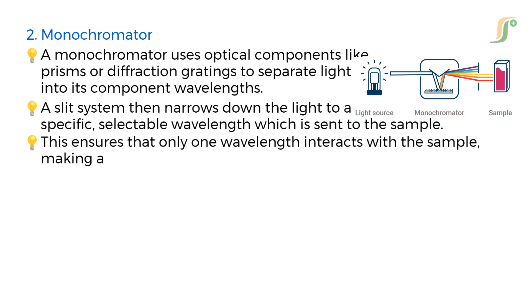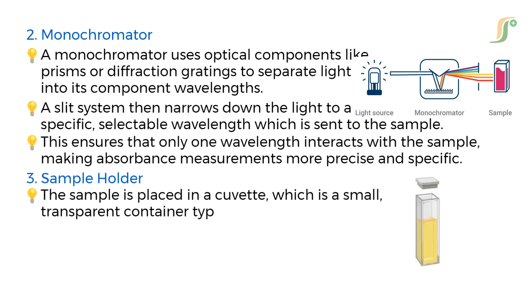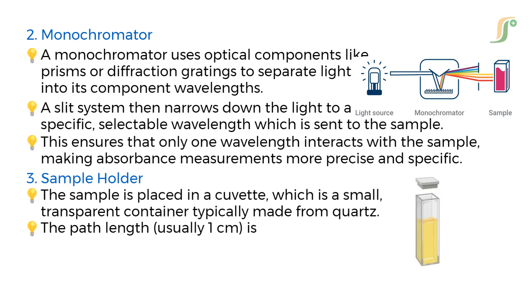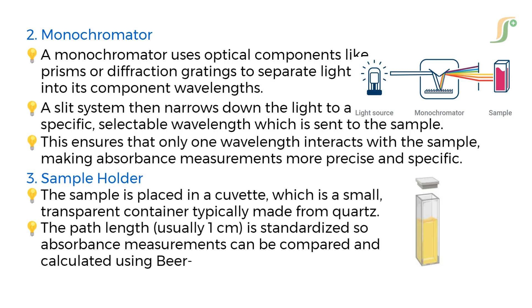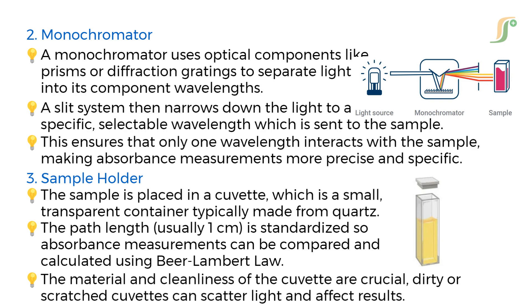This ensures that only one wavelength interacts with the sample, making absorbance measurements more precise and specific. The sample is placed in a cuvette, which is a small, transparent container typically made from quartz. The path length, usually 1 cm, is standardized so absorbance measurements can be compared and calculated using Beer-Lambert law. The material and cleanliness of the cuvette are crucial — dirty or scratched cuvettes can scatter light and affect results.